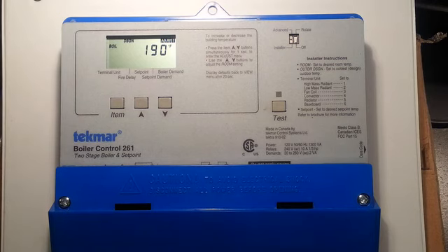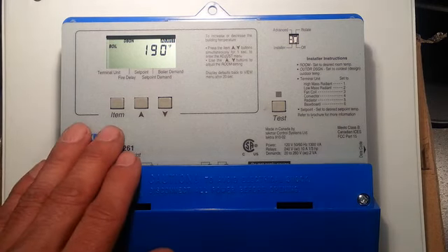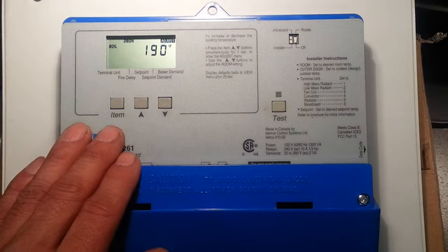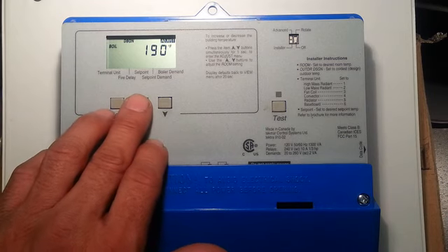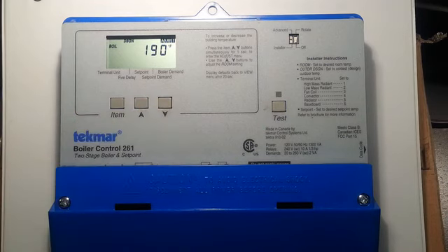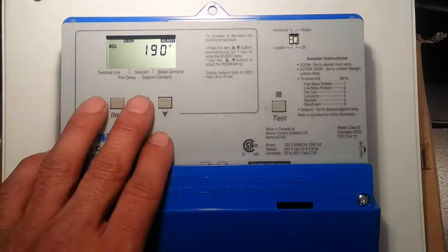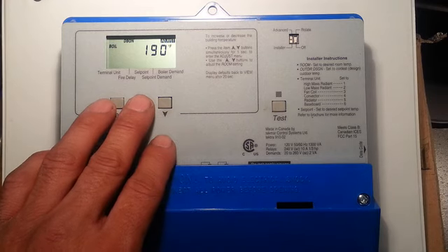Boiler design. This is the temperature that was the maximum temperature during the heat load calculation when the building was built. Now obviously we're not privy to that design condition when it's a retrofit application, so you can typically use, on a 4-story walk-up with leaking balcony windows, set it at the maximum, which is 190 degrees.